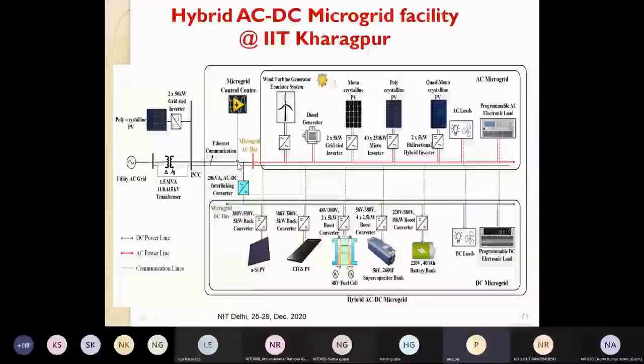The whole microgrid is connected with the main utility AC grid at 415 volt. There is also a 100 kilowatt plant as part of the project at one of the hostel rooftops. However, in our campus, we already have a 1.2 megawatt PV installation done, and another 1 megawatt installation has started. The dotted line shows the Ethernet communication for taking the signal and giving control signals to the individual converters.